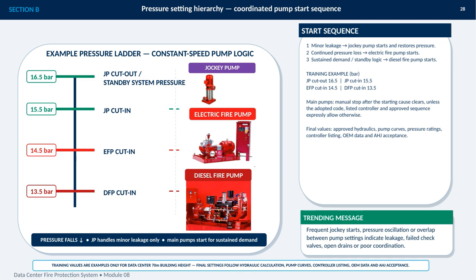Main pumps are generally stopped manually after the initiating cause has cleared, unless the adopted code, listed controller, and approved sequence specifically permit otherwise. These are training values, not final design settings. Final values must follow the hydraulic calculation, pump curves, pressure ratings, controller listing, manufacturer data, and authority acceptance.